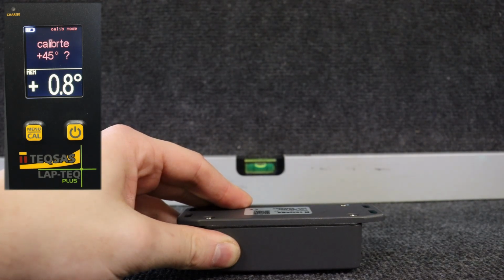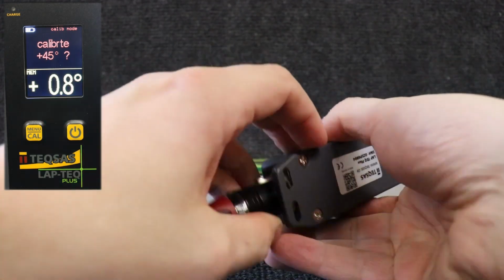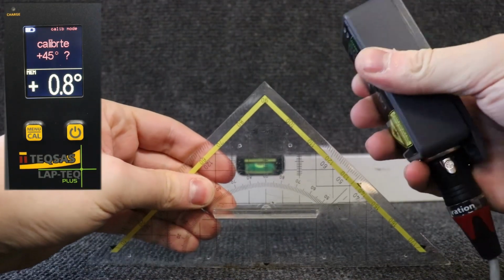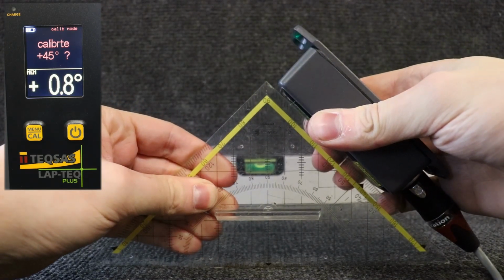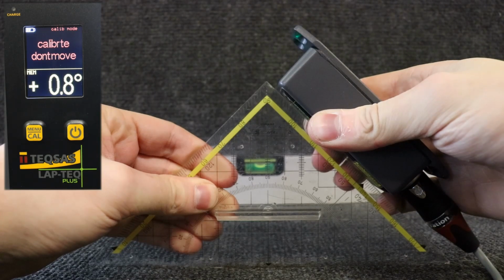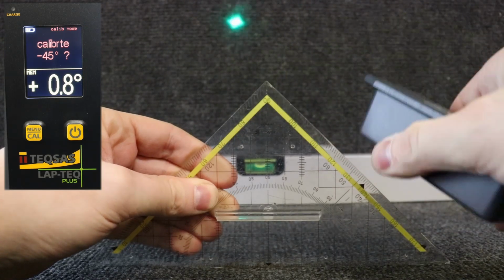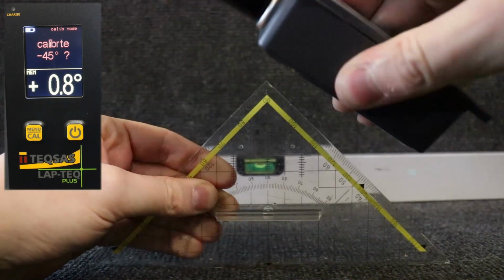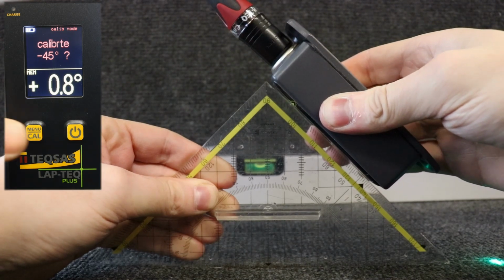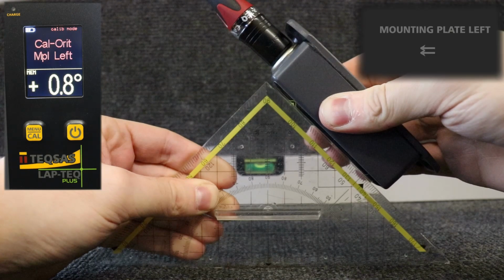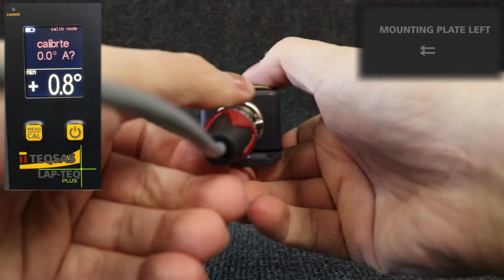Third step is the sensor at plus 45 degrees. And fourth step is the sensor at minus 45 degrees. Again, after a little while, the display confirms that the calibration for mounting plate up has been stored. We could power down now and stop, or we continue in case we want to use the sensor mounted on the side. Third calibration cycle is for mounting plate to the left.